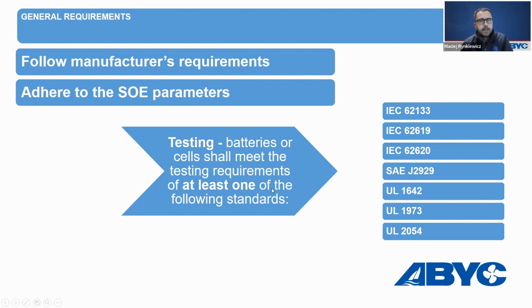As I mentioned before, the quality of the cell is important, because you can have very poor quality cells, and they are available. People buy them from Alibaba, AliExpress, Chinese places, and there are good cells and bad cells. So what we put in the standard is a minimum requirement: the batteries or cells shall meet the testing requirements of at least one of the following standards, either IEC or UL standards. The RV industry already requires that, so a lot of battery manufacturers already comply.